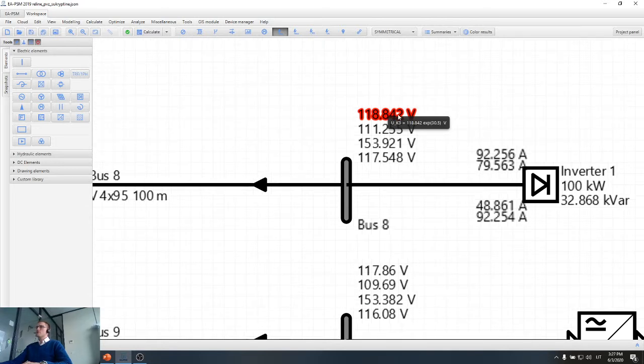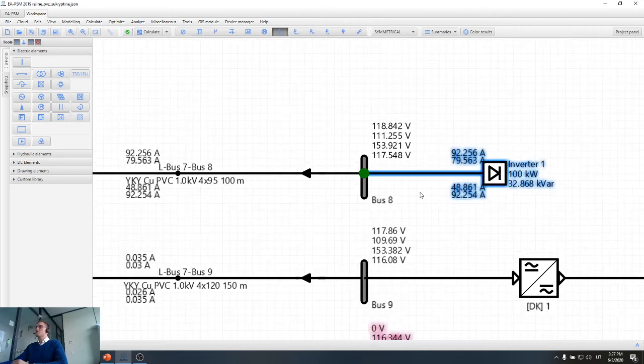so much smaller than 230 volts. Then in two-phase we will have a voltage equal to 111. In one phase the voltage will be equal to 153, and in two-phase with ground it will be around 117.5. So we can see that in all of these possible scenarios the voltage will be much lower than nominal, and after some time the inverter will automatically disconnect. What is more, we know that during short circuits voltage becomes unsymmetrical, and unsymmetrical conditions are also very bad for the inverter, and therefore the inverter already has protection from that.